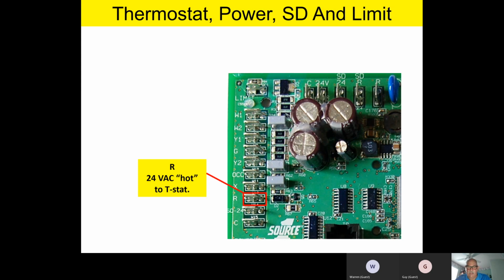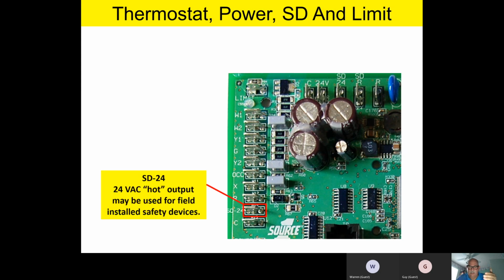Below that is our 24-volt hot to the thermostat, that R terminal. Again, that's extremely common in our industry. R is 24-volt hot. Now you'll notice that on the thermostat terminals, there's a parallel SD24 circuit. It may be used for field installed safety devices, but what I'm going to recommend is just leave that alone, even though, if you look at that block diagram in that previous slide, it's just a parallel circuit. So one of the things I'm going to ask that you do is just leave that terminal open. Don't do anything with it.